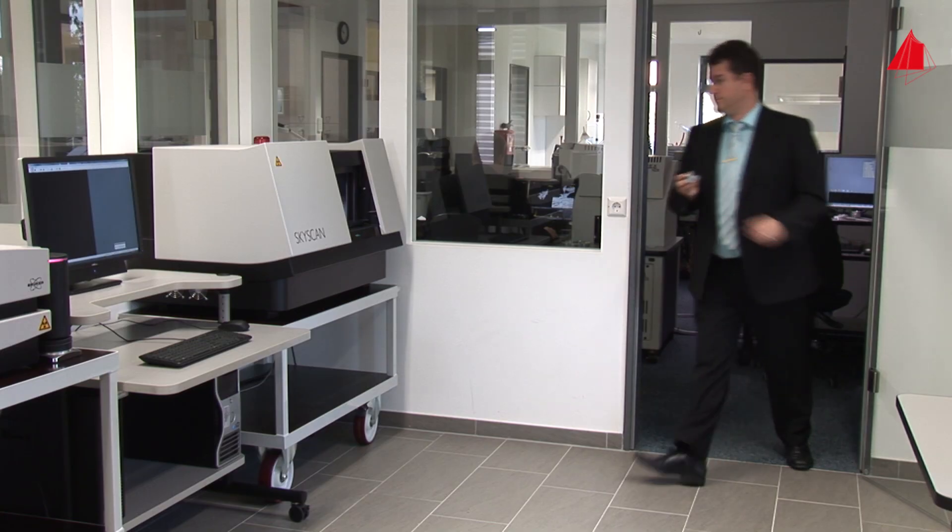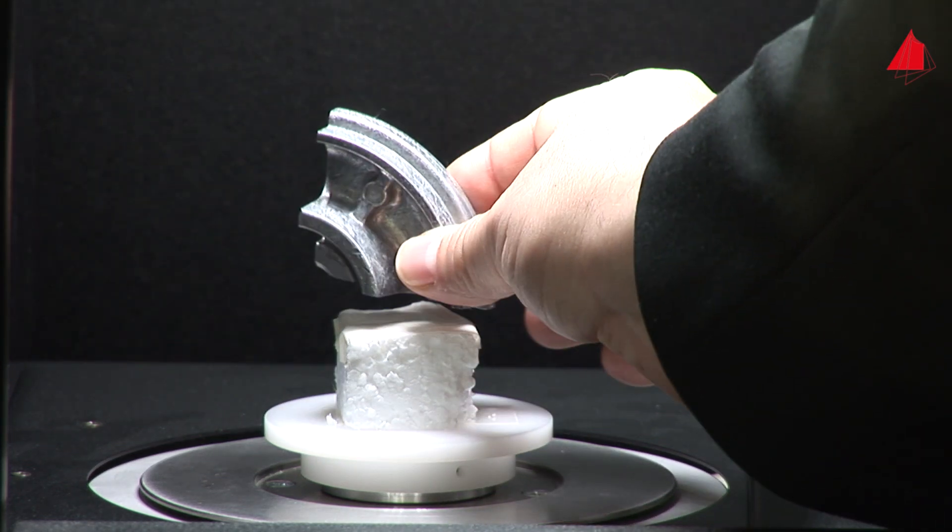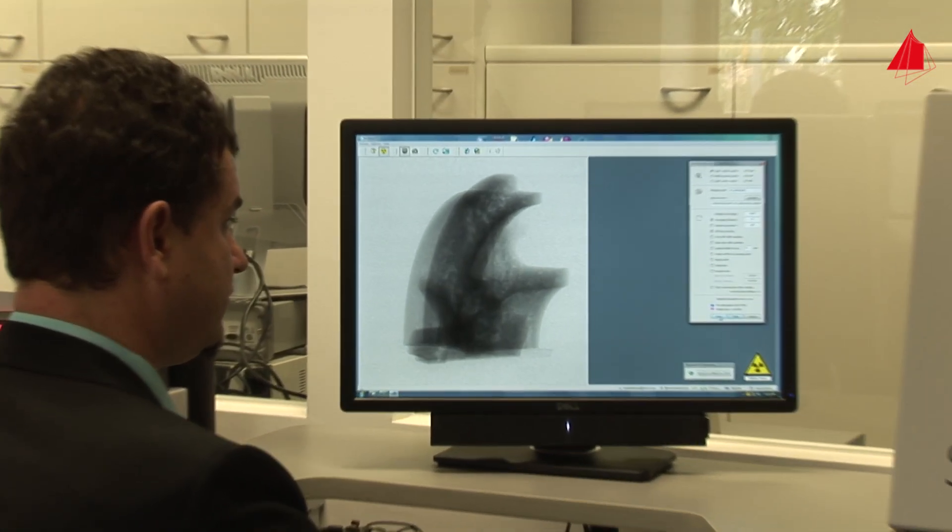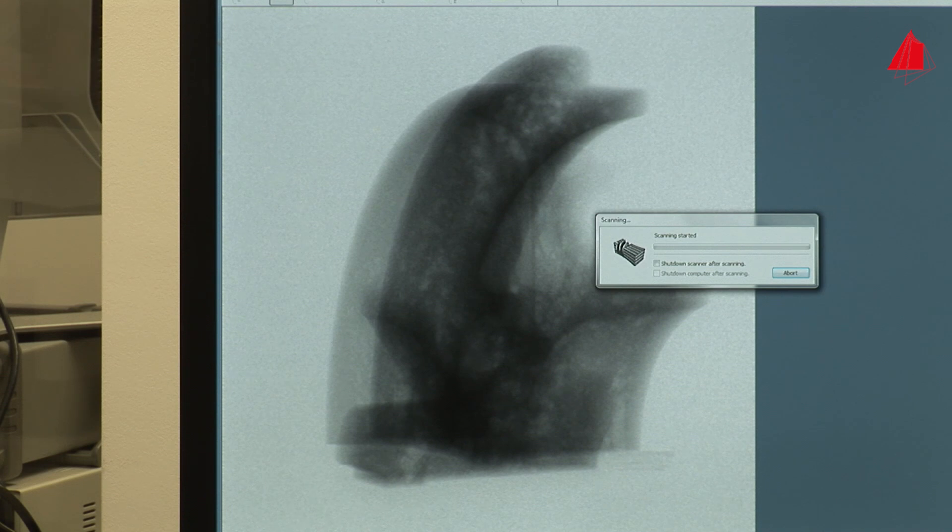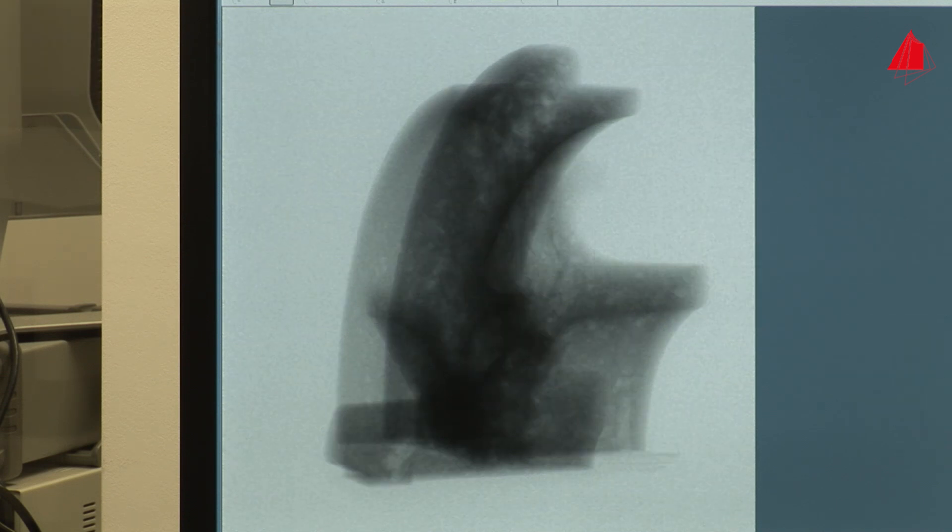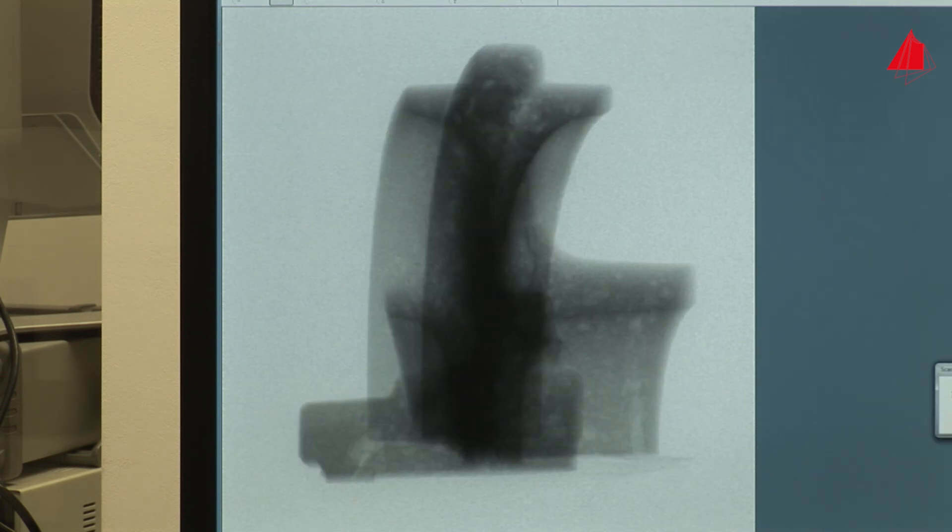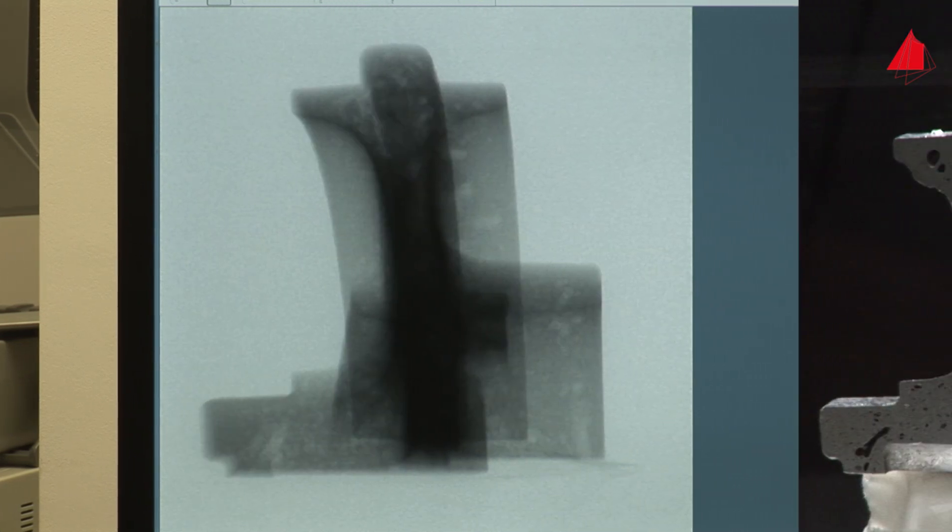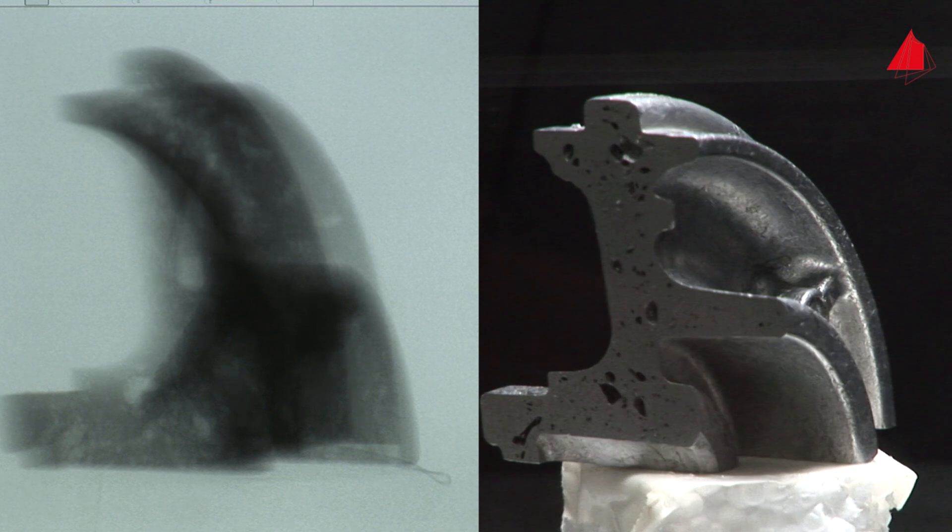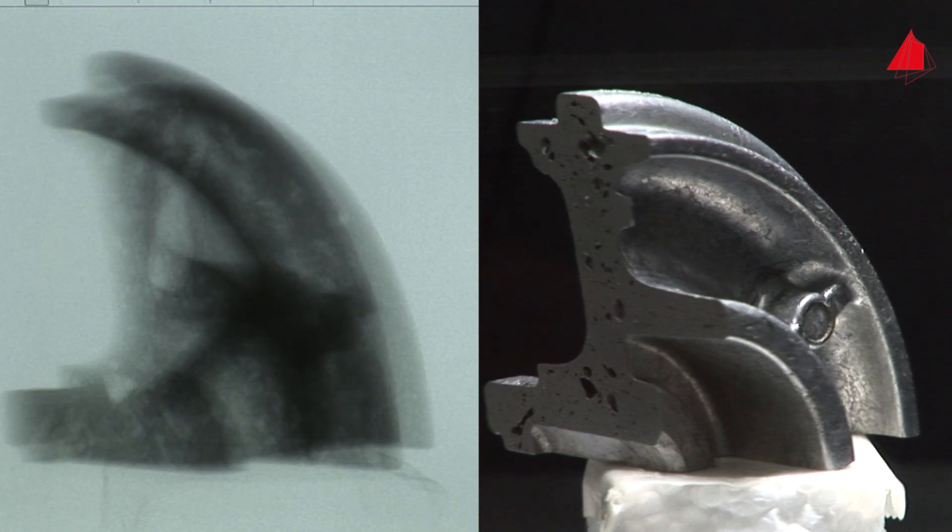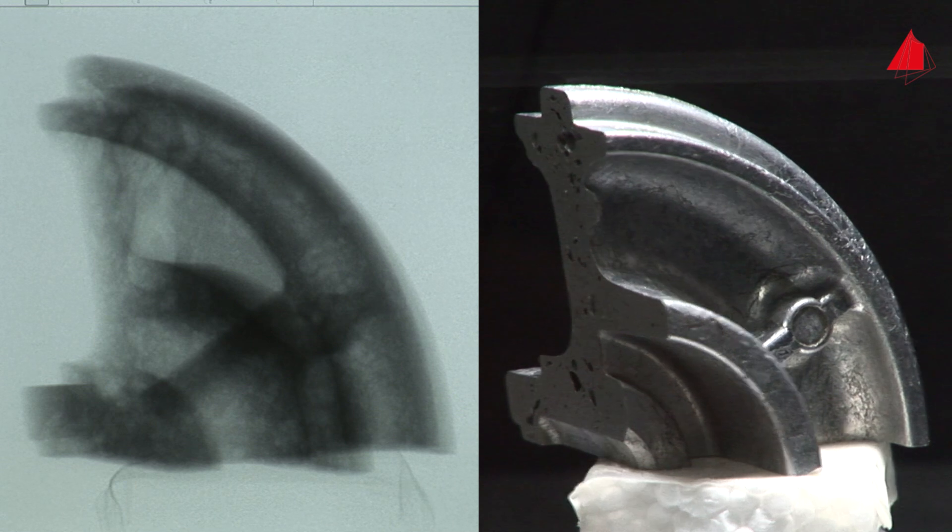And here we go. We want to examine part of a die cast sample made of an aluminum alloy. Shortly after the start, the first x-ray images can already be seen on the monitor. After recording one x-ray image, the sample is rotated slightly and the next image is taken. The resulting x-ray image files are also called raw data sets. Later on, the raw data sets enable a reconstruction of the individual cross sections and, based on them, the calculation of the computer model.